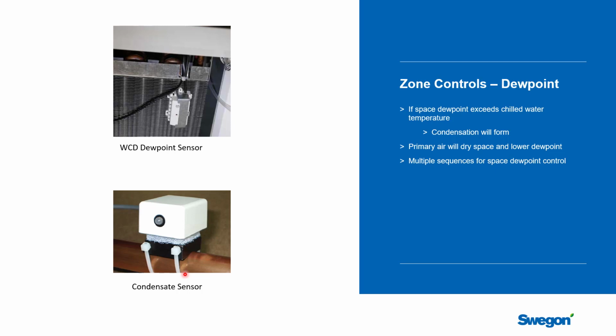That primary air will be selected, its psychrometric conditions selected so that it will provide a drying effect in the space. Now this is a constant volume system, and so you're going to get full drying effect all the time, whether you need it or not. So whether it's a low humidity load in the space or a high humidity load, you'll have the design amount of primary air going into the space, and so you're going to have maximum drying effect.